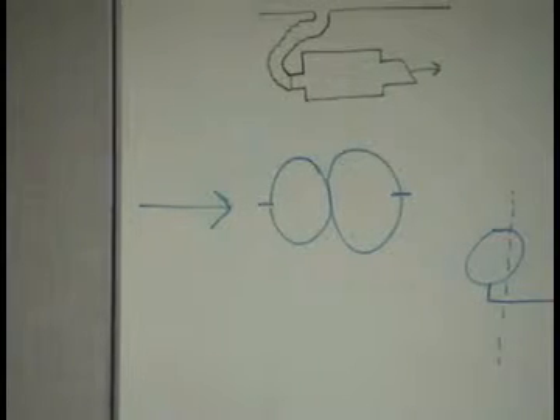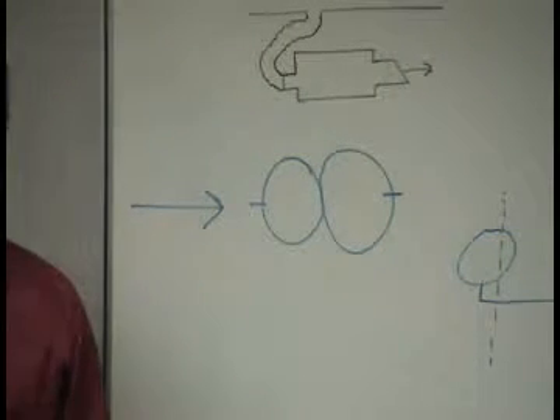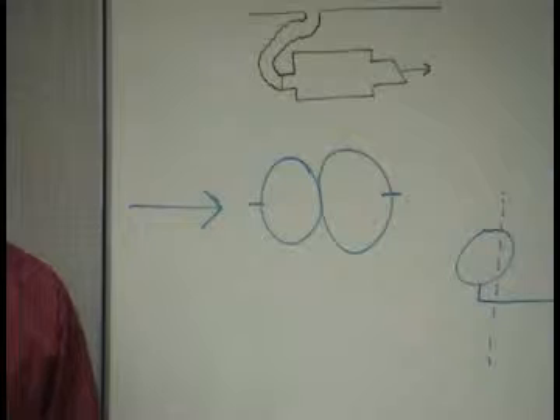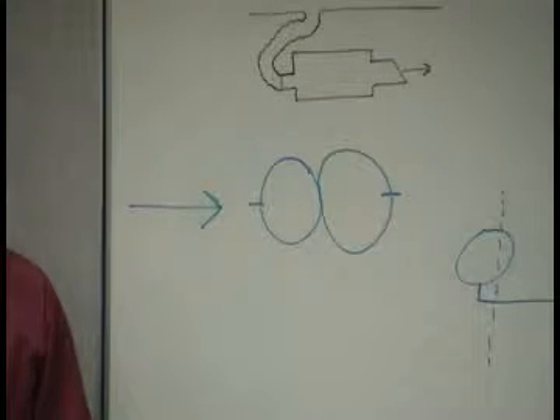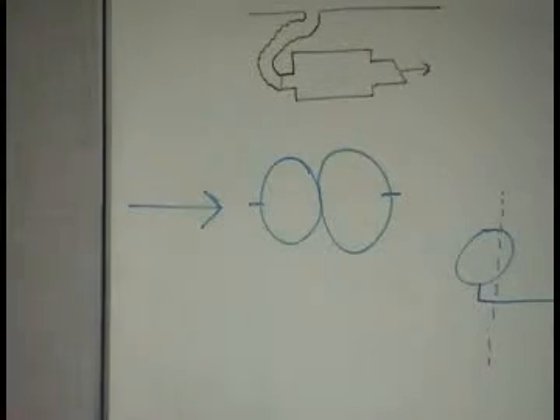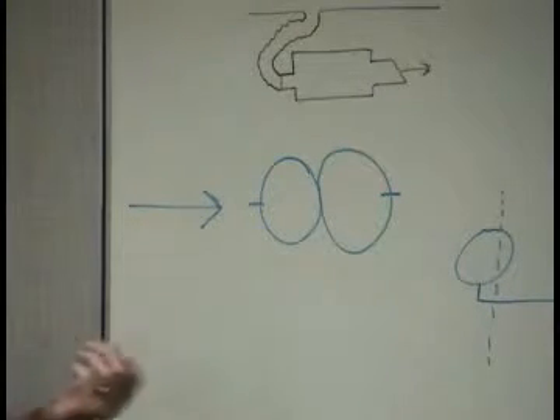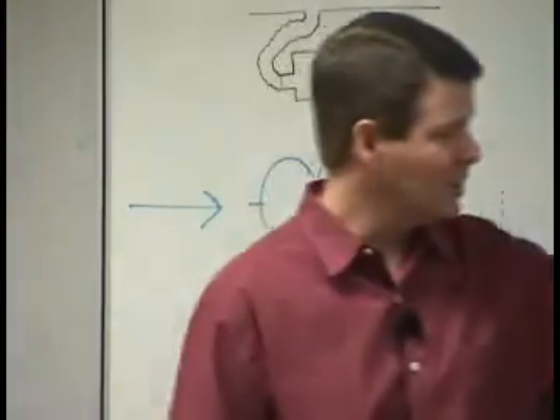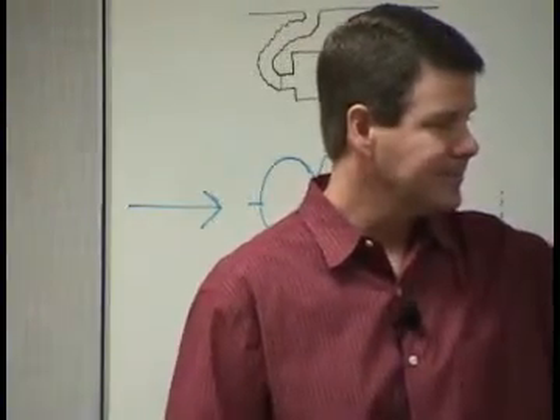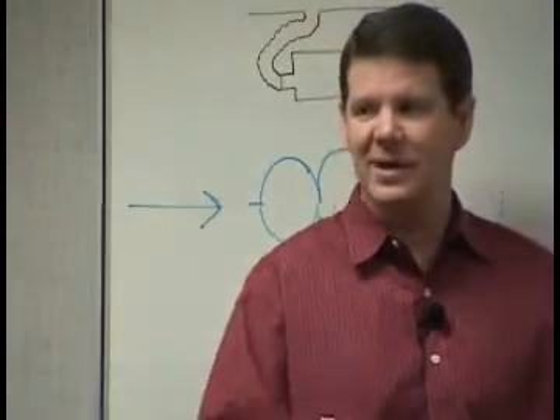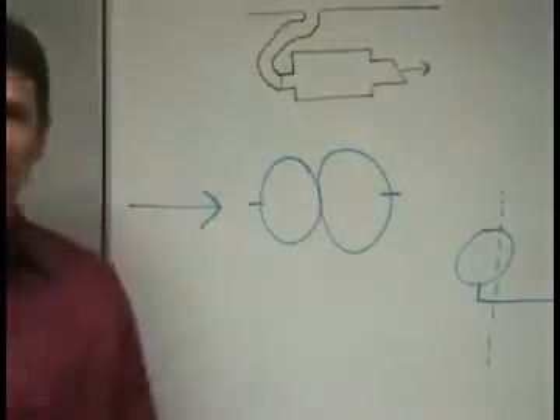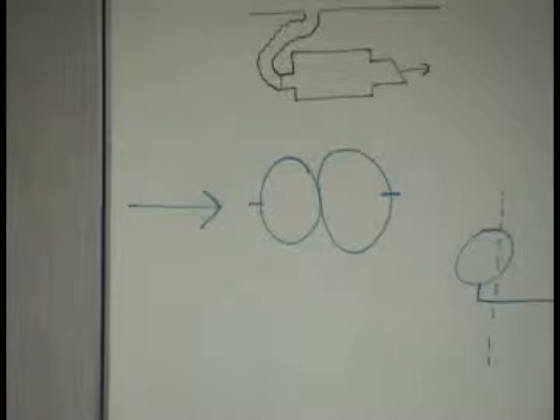And if, like Mick was saying, you have a great difference in temperature, you've about eliminated any possibility of it ever happening. The closer they are in temperature, the better off you're going to be. But somewhere in the middle, you come down to a point where you get more velocity out of there. And when you have more velocity through that hot water coil, it's also cooler because we're not heating it as much. So, it's kind of a double benefit.